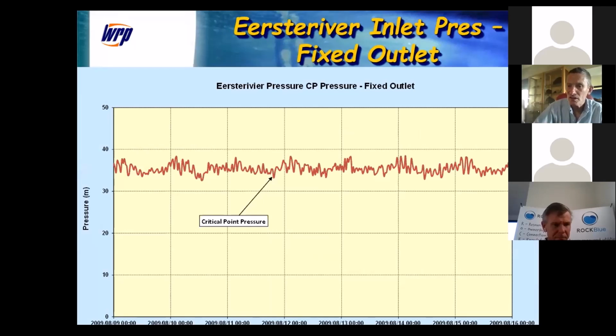Now you could still take it down further. You could take it down probably to about 20 if you really wanted without having a riot on your hands. But anything below the 38, we were worried about getting complaints. The client didn't want complaints. So a lot of the time you get a balance between complaints and high pressure. So we settled on 38 meters.